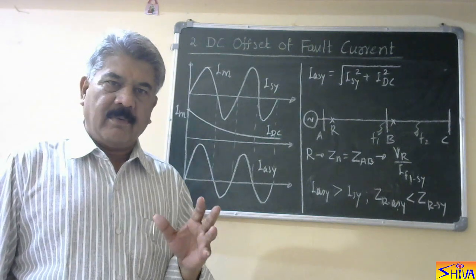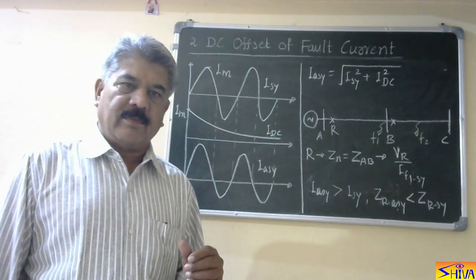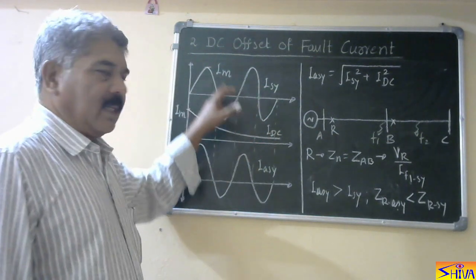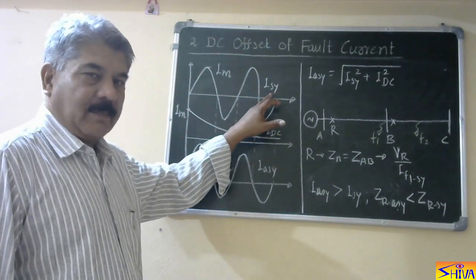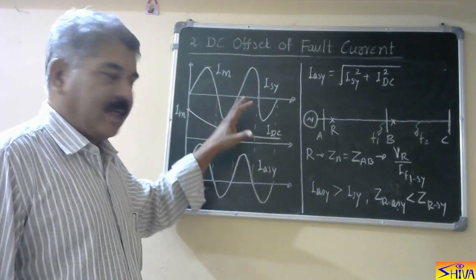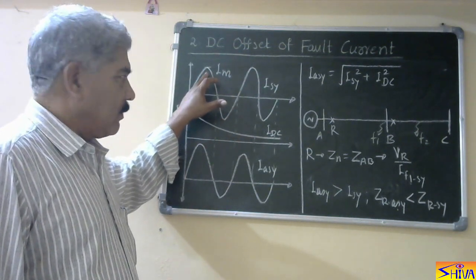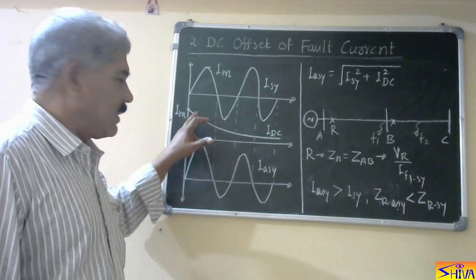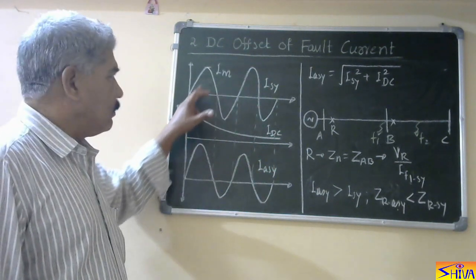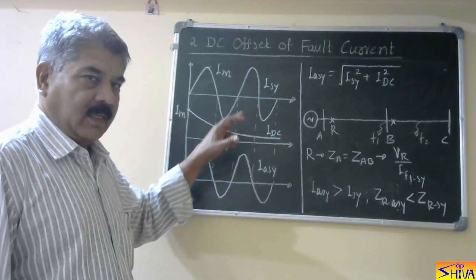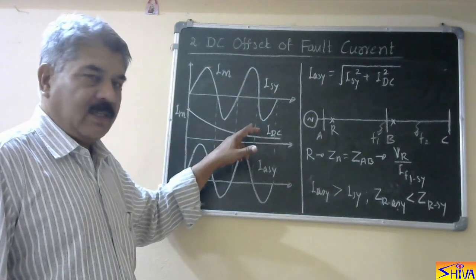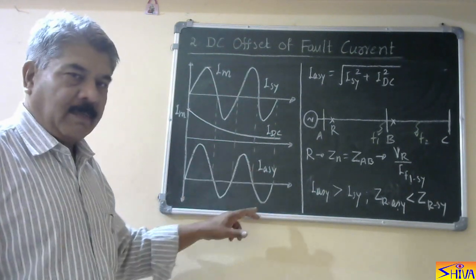First, I will explain briefly what is DC offset of the fault current. When the fault current is symmetrical, the positive half cycle and negative half cycle are equal in magnitude, with peak value Im. When DC offset is present, it is exponentially decaying and in the worst condition it can go up to the peak value of the symmetrical component of the fault current. So the actual fault current is a combination of symmetrical fault current and DC offset, and the resulting waveform will look like this.